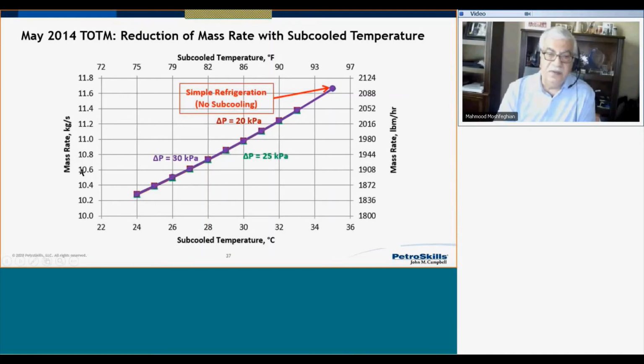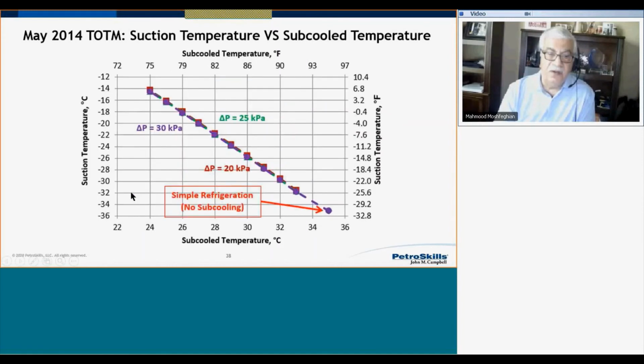This is the mass flow rate as a function of subcooling temperature. With no subcooling, the temperature was 35 degrees C, this condensing temperature, and it's saturated liquid. If you do subcooling, lowering the subcooling temperature to this low value, the mass flow rate goes down, which is favorable, even though I have a different pressure drop in the heat exchanger on the gas side. My mass flow rate goes down, which is favorable.